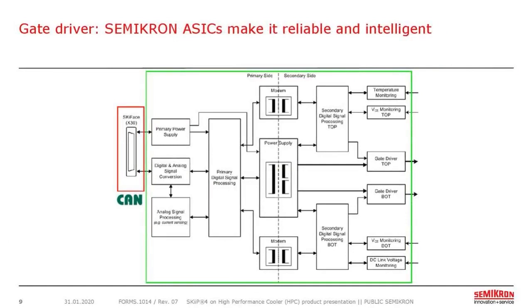The driver is one of the core elements of the SKiiP4. The fundamental function is safety isolation from the primary side to the secondary side, which we facilitate with transformers. This gives a very reliable, robust separation of signals with very high isolation and safety. It's a typical dual channel design: one complete driver for the top side and another for the bottom side, with those two independent drivers connected on the primary side through this interface.